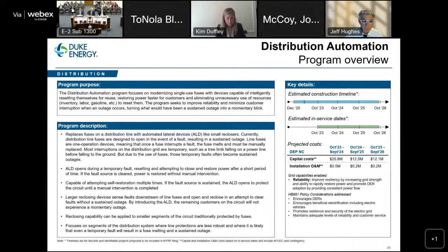Most faults on overhead distribution systems are temporary faults. A couple of examples: it may be a limb falling from a tree that temporarily brushes the line and continues to fall to the ground, or it may be an incidental animal contact. Those also tend to be temporary faults on the system. The challenge with that traditional fuse, just like in your grandparents' fuse box, is if the fault magnitude is high enough or it's just long enough, the fuse does what it's supposed to do - it opens up and protects the lines or circuit from further damage. But it's a temporary fault.